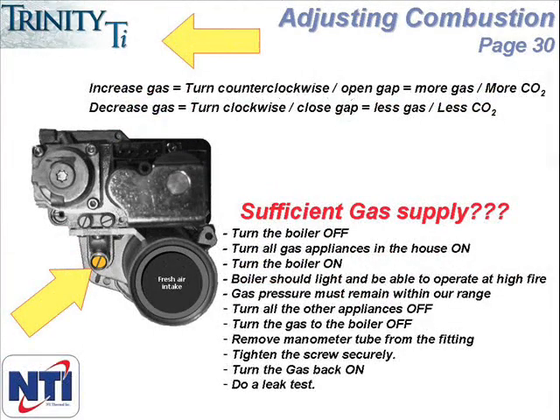Once you've completed the combustion analysis, there is one more quick test to make sure everything is operating properly. Make sure the boiler is not running and turn on all the other gas appliances in the house. Then go back to the boiler and get it to fire — it should light properly and remain lit at high fire. This is why I mentioned keeping your manometer hose connected, because the line pressure needs to stay within the acceptable range when all appliances are running.